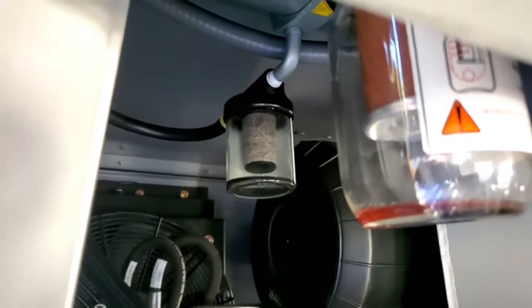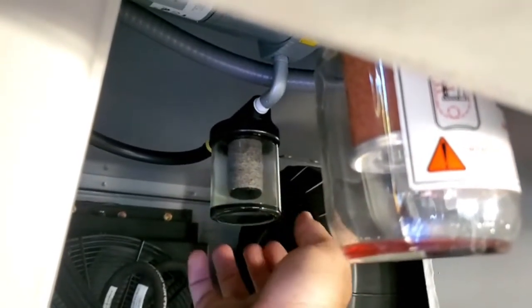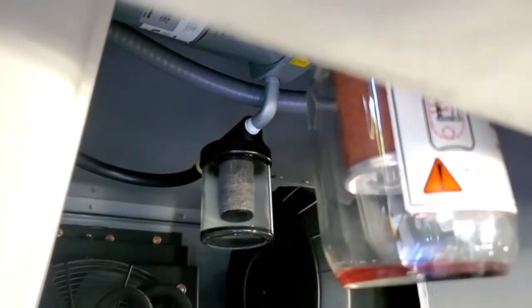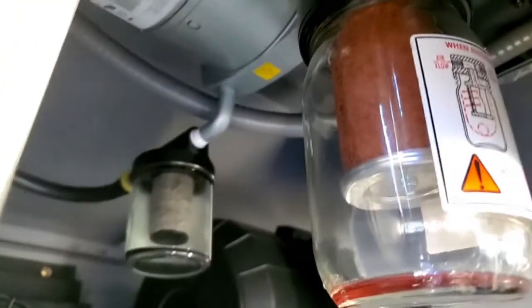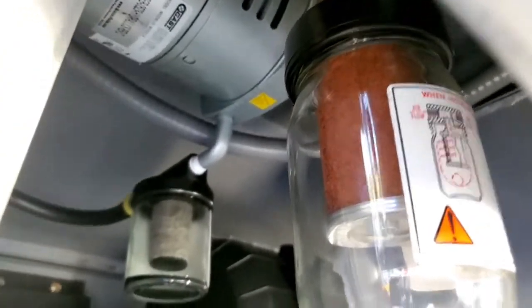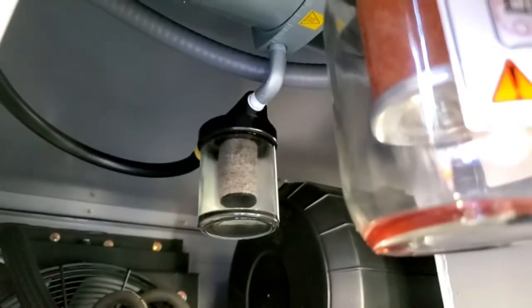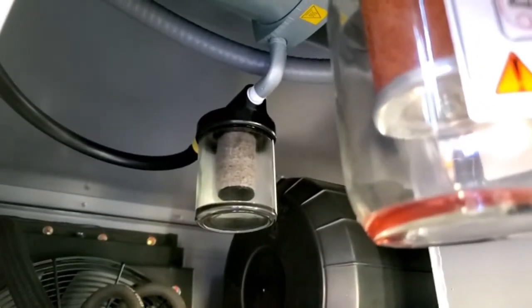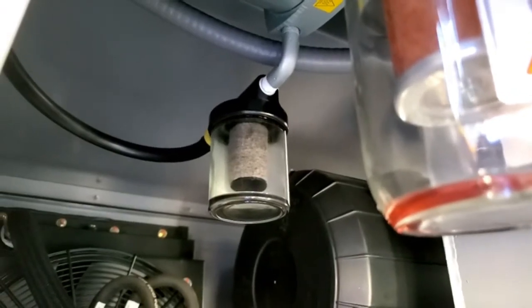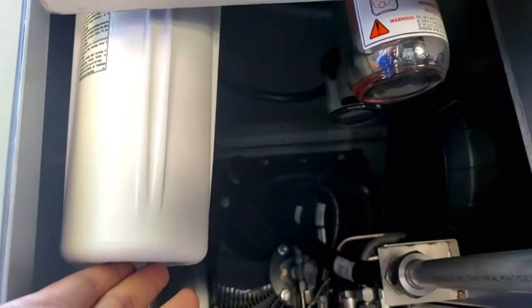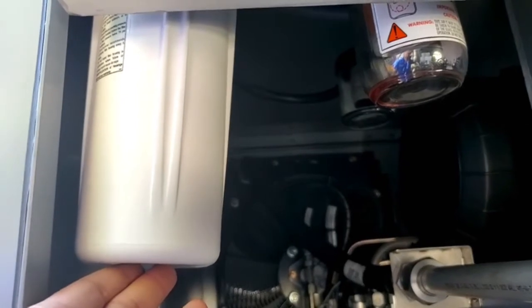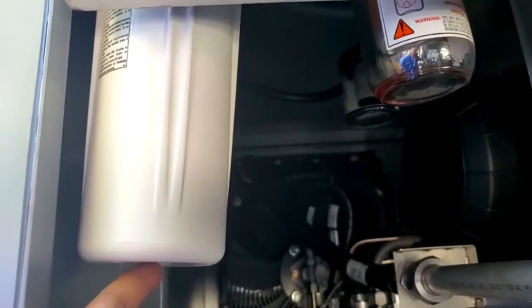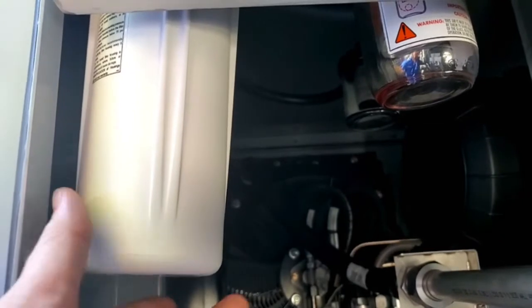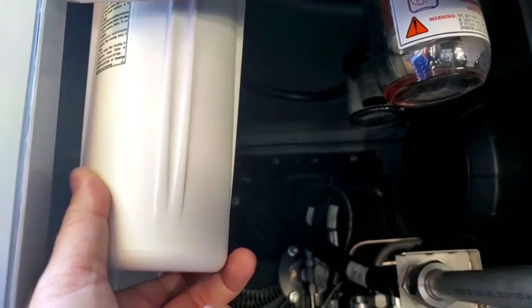On the outlet side of the vacuum pump, you'll find this other glass jar here. This glass jar is to catch the oils and vapors that are coming past or through the vacuum pump, and they collect in that jar there. That jar will not fill up very fast at all and should be cleaned out periodically. After this glass jar, it comes over to your odor filter right here. When you purify hydraulic fluid, it creates a very nasty smell. So inside of here is a filter that will clear the smell and not create a stench coming from your unit during purification.